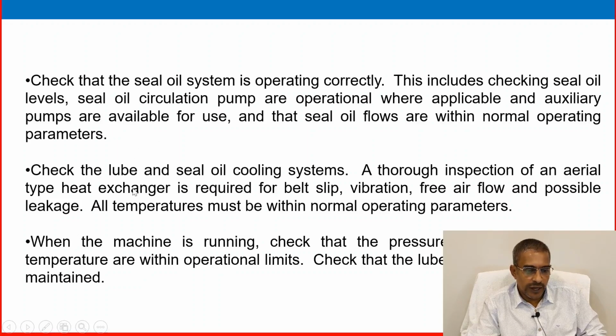Check the lube and seal oil cooling system. A thorough inspection of an aerial type heat exchanger is required for belt slip, vibration, free air flow, and possible leakage. All temperatures must be within normal parameters. When the machine is running, check that the pressures, level, flow, and temperature are within operational limits. Check that the lube and seal oil levels are maintained.